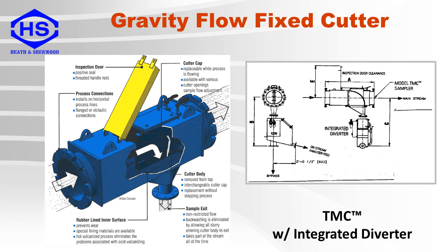This is an example of a launder sampler which is a top mounted cutter, or TMC. These are used for slurry applications and are designed for process lines which are not under pressure. The TMC has a cutter which is placed in the middle of the slurry flow in order to extract a portion of the material. The extracted sample then goes through the exit nozzle, and the main process flow exits to the main part of the sampler.